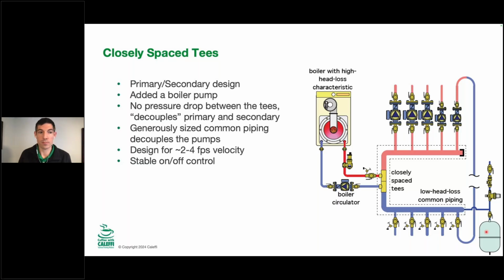So just going forward, when you're talking to somebody about primary, secondary, maybe that's the first question you'd ask. Well, where's your expansion tank in the system? And then, well, we're calling that the primary loop. So we're both talking about the same thing. Yep, and that's a good point. And sometimes to avoid confusion, like you said, you can say, are we talking about the boiler loop here? Or are we talking about the distribution loop? If there is confusion about whether you are talking about the left or the right when you say primary, that is the book answer for which one. But also, if that helps for whatever conversation you're having, use: are we talking about the boiler or heat pump loop? Or are we talking about what's going out of the mechanical room? Just to clarify that, so you're not troubleshooting the left versus the right and running into an issue there over the phone or something like that.